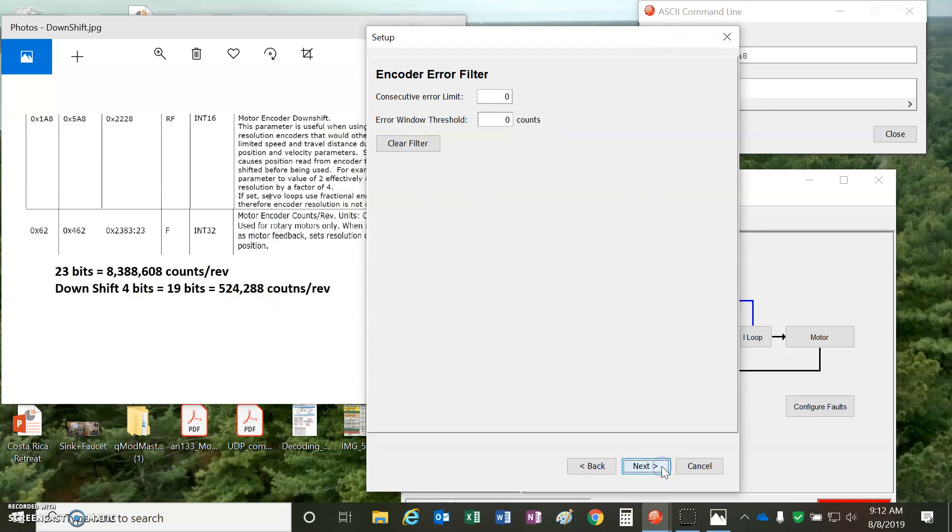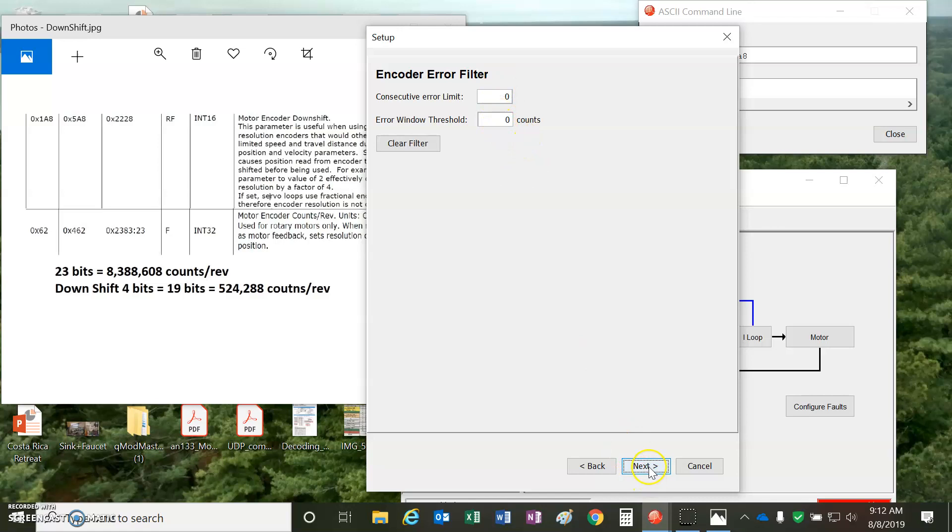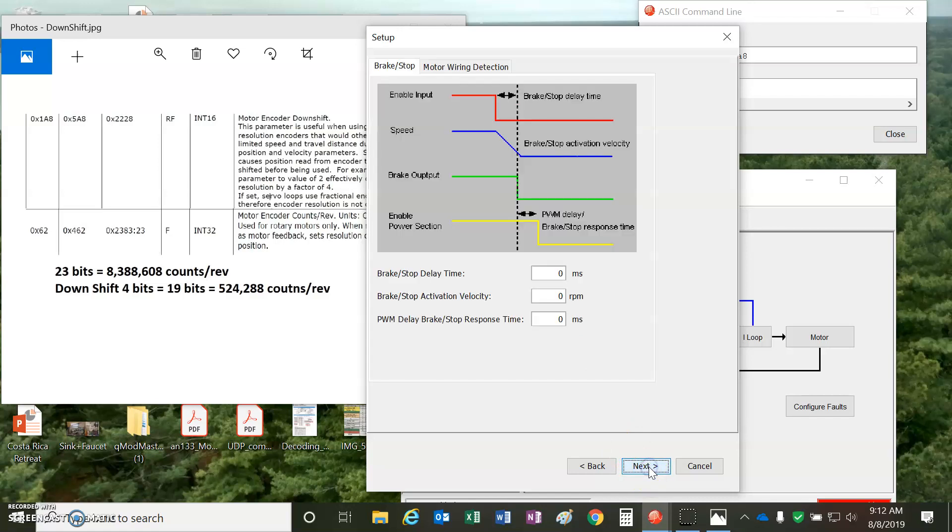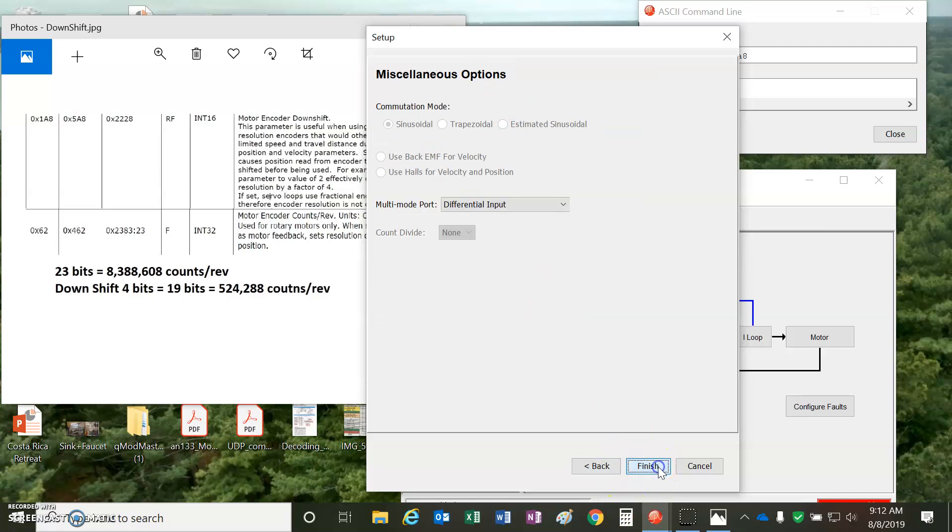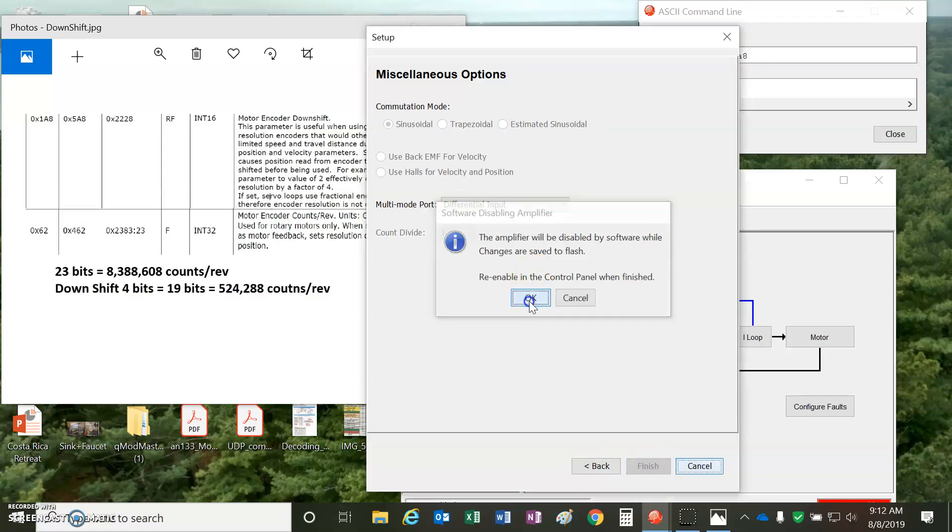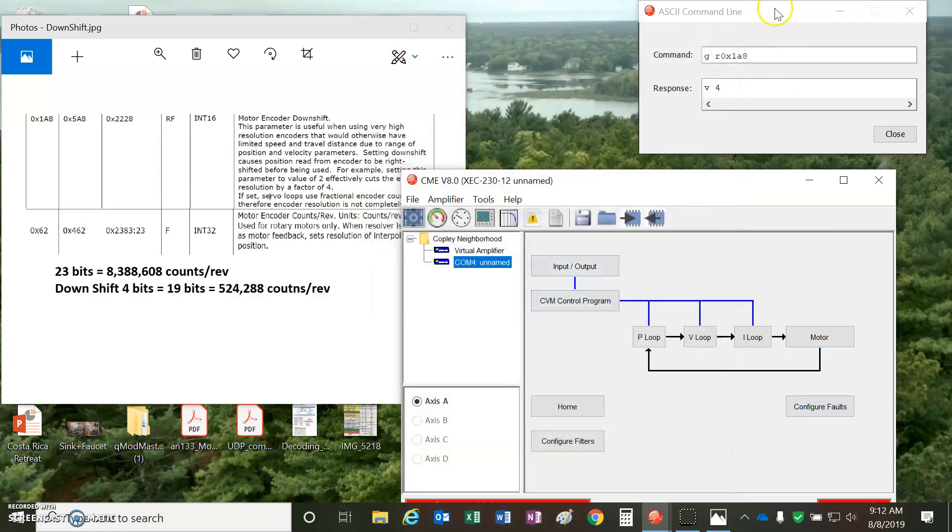So after we get the basic configuration set, if there were CRC faults, we could ignore them. But I don't like to ignore CRC faults. I didn't get any CRC faults. I guess if there's a lightning strike, you might get one, so you could ignore one with a window. And then for stopping, there's a controlled stop. This is just going to be position mode, EtherCAT. And that's the configuration.